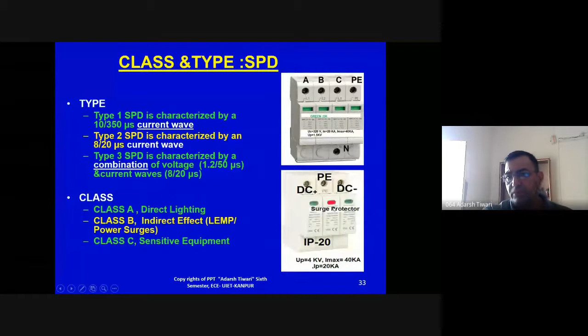So whenever we are putting any SPD, we have to see which type and which class. Now if we see class A is for the direct lightning, class B is for indirect effects or surges, and class C is for sensitive equipment. Now these surge protector devices come in AC, ABC phase, and this is protective earth, and this is the neutral. And it also comes if there is plus minus DC. Now it may have color indication, like if you see the top figure, all are green, that means every phase is protected. Now if there is something red, visual protection, it means that surge protection is out.